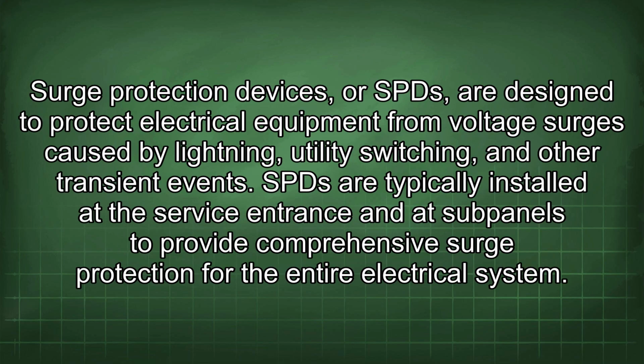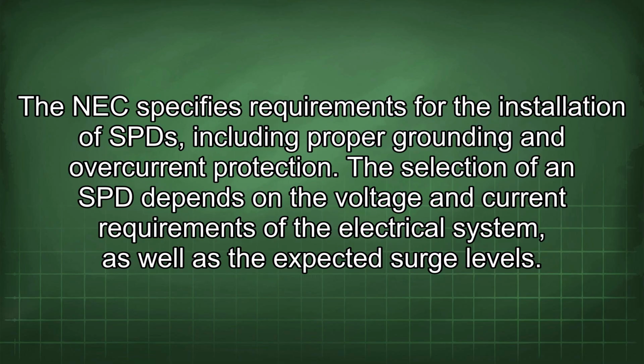Surge protection devices, or SPDs, are designed to protect electrical equipment from voltage surges caused by lightning, utility switching, and other transient events. SPDs are typically installed at the service entrance and at subpanels to provide comprehensive surge protection for the entire electrical system. The NEC specifies requirements for the installation of SPDs, including proper grounding and overcurrent protection.